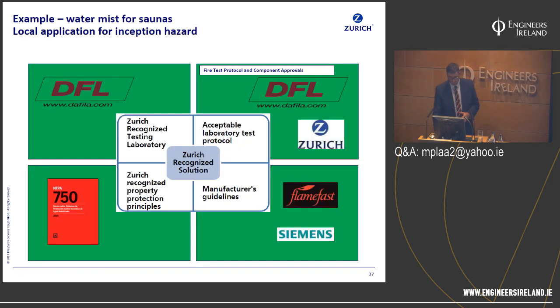In terms of the Danish testing, what would they have tested? Is there sort of a typical sauna setup? Yeah, so that's a really good question. What happened in that case is we developed a reference test. We used a single K80-141 sprinkler head, undertook a test in a sauna that measured 3 by 2 by 2, and then undertook fire testing of that. So we had some base data for a sprinkler, and then repeated that test multiple times with a water mist head to see if it was equal to or better than the sprinkler head.